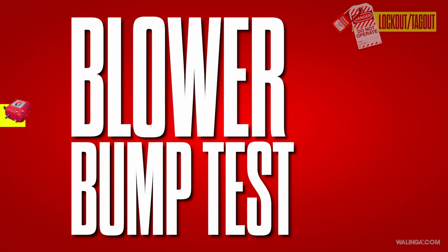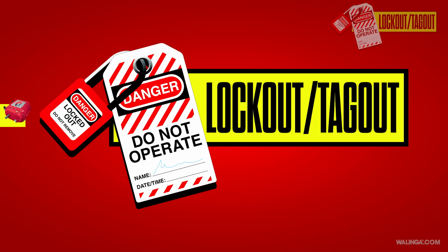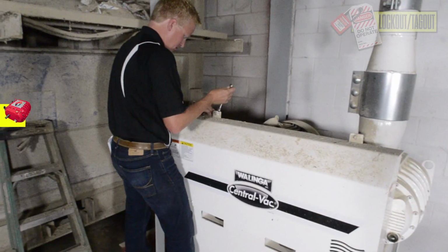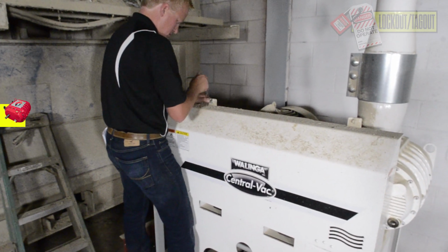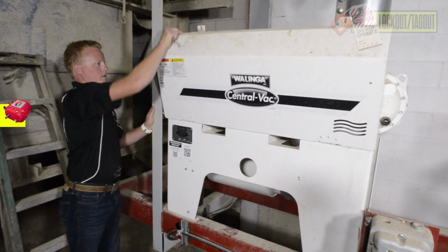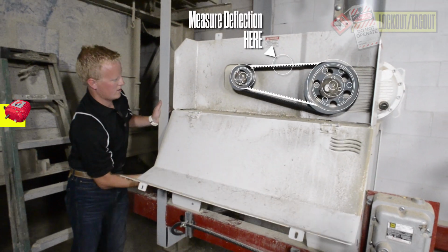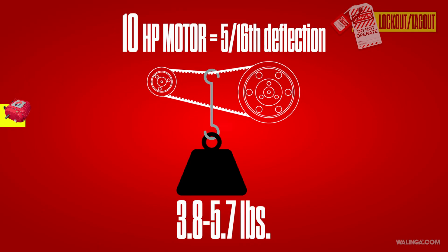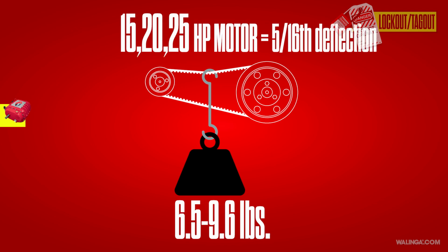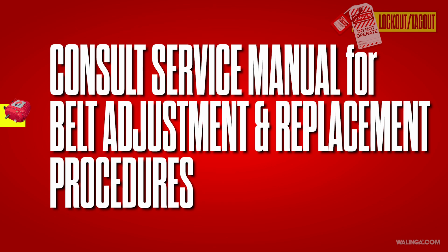Blower bump test. Remove power, lock out, tag out the power source. Remove belt cover 9/16" bolt, open hinge cover forward. Check belt condition and tension. Tension should be 5/16 inch deflection, with 3.8 to 5.7 pounds weight for 10 horsepower motor, and the same 5/16 deflection, but with 6.5 to 9.6 weight for 15, 20, and 25 horsepower motors. Consult service manual for belt replacement and adjustment procedure.